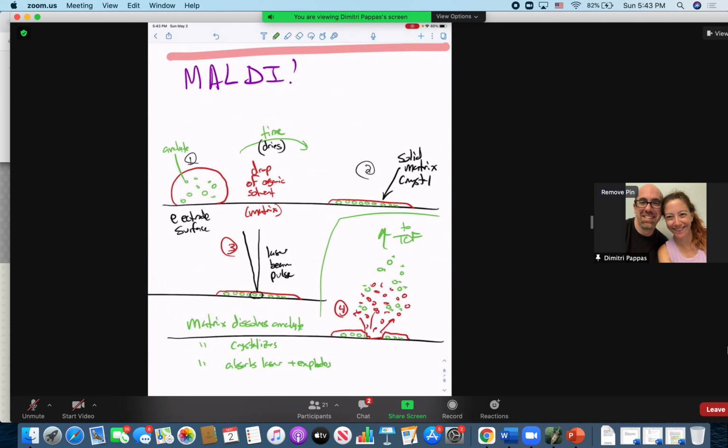And the reason for that is MALDI makes large, intact M over Z ions, right? Large M over Z intact ions. So the mass to charge ratio of ions produced in MALDI can be hundreds of thousands of Daltons, even up to a couple of million Daltons, giant molecules. And the other mass analyzers can't handle ions of that size. Time of flight can handle any size ion because it's limited by how long you wait for the ion to traverse the field. And we're talking about far less than a second to complete an entire mass spectrum of all possible mass values.